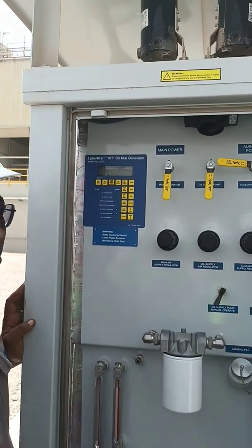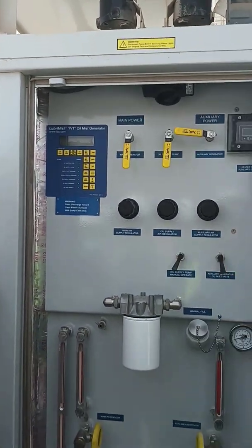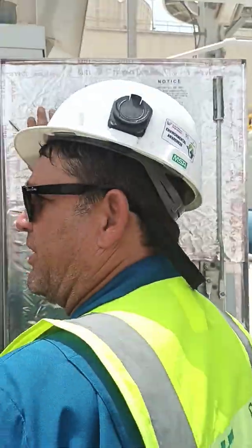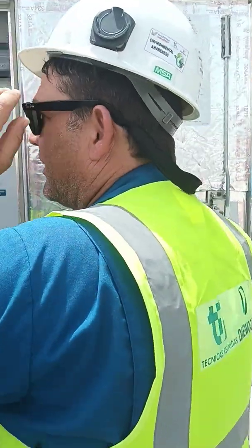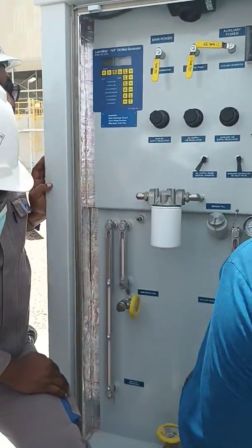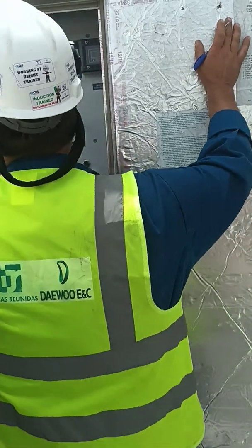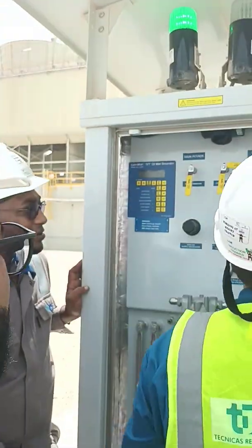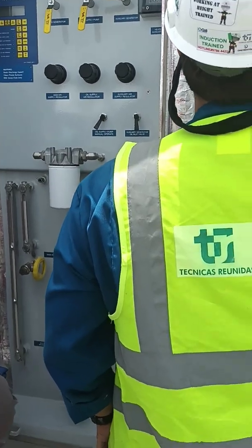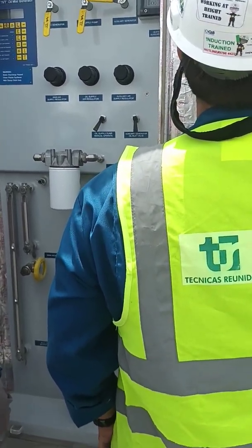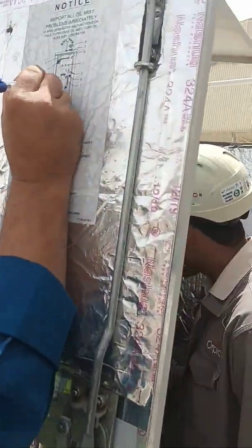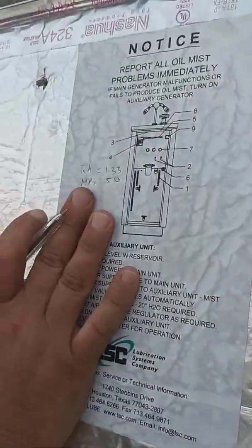I'm going to write down here. This machine normally has a sticker where you write down the commissioning readings when we started the machine. So in 10 years time, that should be the same. For example, I don't care about my air temperature. What I care most is the regulated air. It is 1.33. Okay. This pressure is 50. And that is, for me, the main thing.